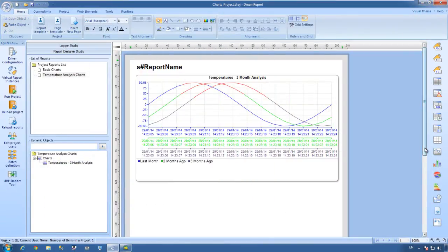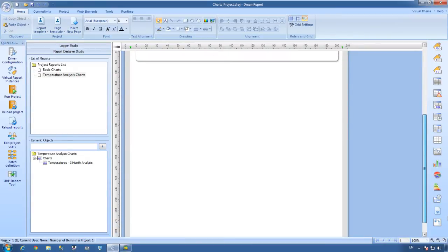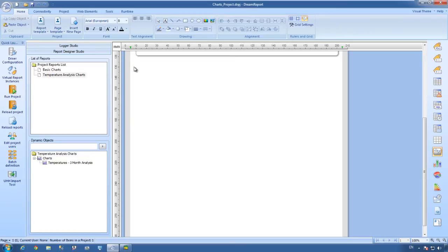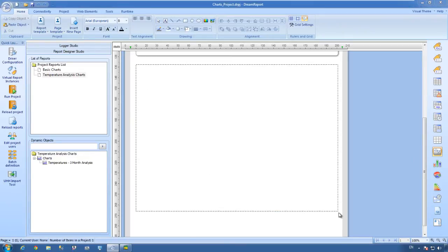In this third use case, we'll create an energy signature chart, which links energy consumption to ambient temperature so that a building's sensitivity to temperature can be monitored. It's a special XY chart where the y-axis displays energy consumption and the x-axis displays external temperature. We plot this line as a linear regression instead of just raw values, and we will use a line with markers for the line style.